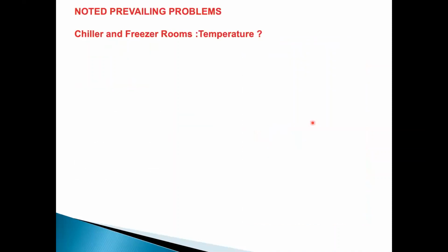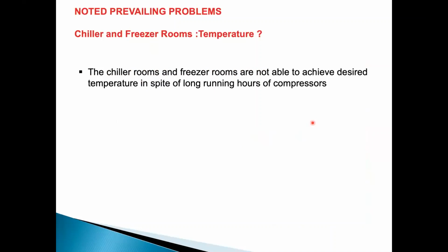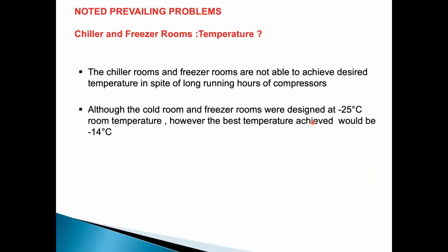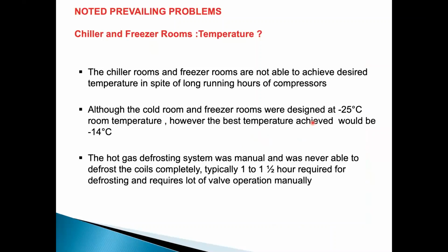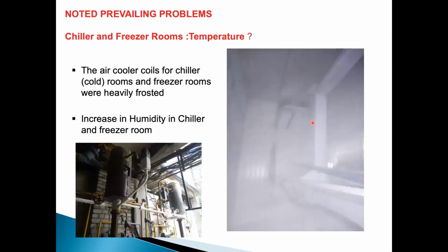In the cold rooms, the freezers and chiller rooms, the biggest problem was temperature. The desired temperature of minus 25-26 degrees was never achieved. The lowest temperature achieved was minus 14. A manual hot gas defrosting system was provided, but it was not able to defrost. You had to run it for 1.5 hours or sometimes 2 hours and operate all the valves manually, and there was always a possibility of gland leakages and other issues. When this system was operated manually, the temperature rose by 10 degrees. Minus 14, minus 15 used to go up to minus 5, so you had to run again for a longer time to cool down.